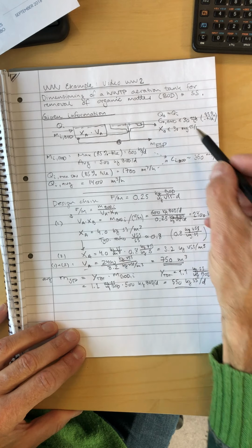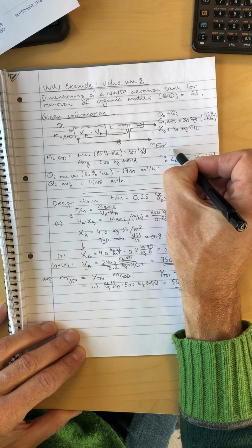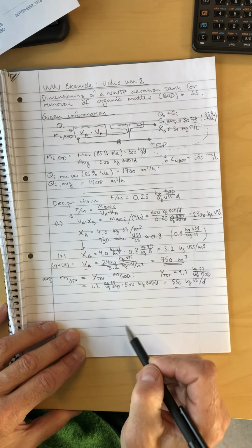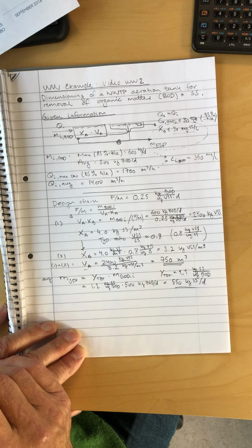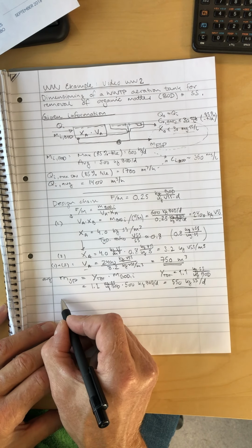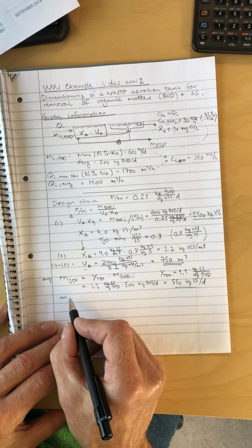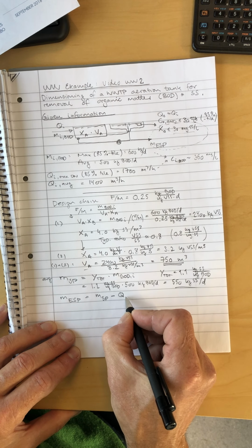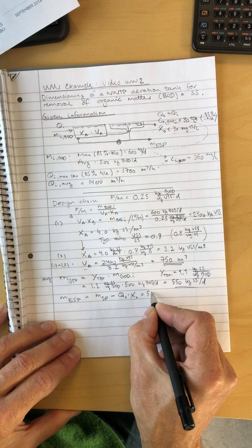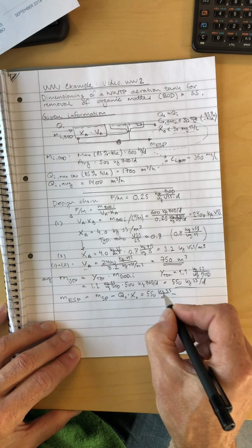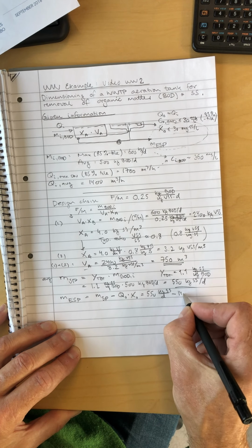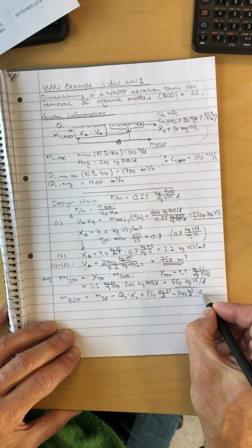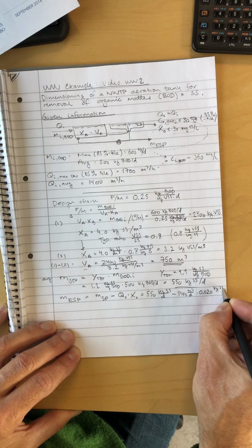Now the sludge production is the sum of the excess sludge production and the sludge in the outlet. Looking at what I've got here, I could maximum have 30 milligram per liter, so probably on average I will have something less than that. So the excess sludge production is the total sludge production minus the amount of suspended solids in the outlet. So that's the 550 kilograms suspended solids per day minus an average flow, 1400 cubic meter per day, and then something probably a little less. Let's assume I have 20 milligram per liter, so 0.020 kilogram suspended solids per cubic meter.